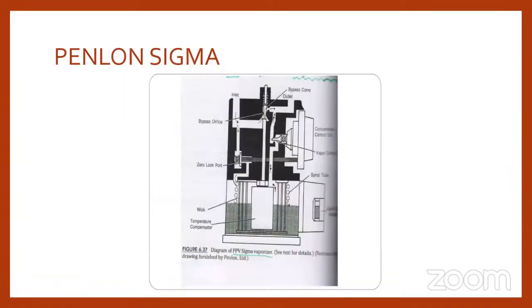Other companies have already developed other types of vaporizers. The major principle is the same. This is the flow diagram of the Penlon Sigma vaporizer, which has a vaporizing chamber with a zero lock port bypass. It is also a bypass system. This is the fresh gas direct flow, and this is the bypass system. This is the rotator knob. Whenever we want to increase the flow, we rotate this dial, so the anesthetic agent that mixes with the air will be more in this kind.